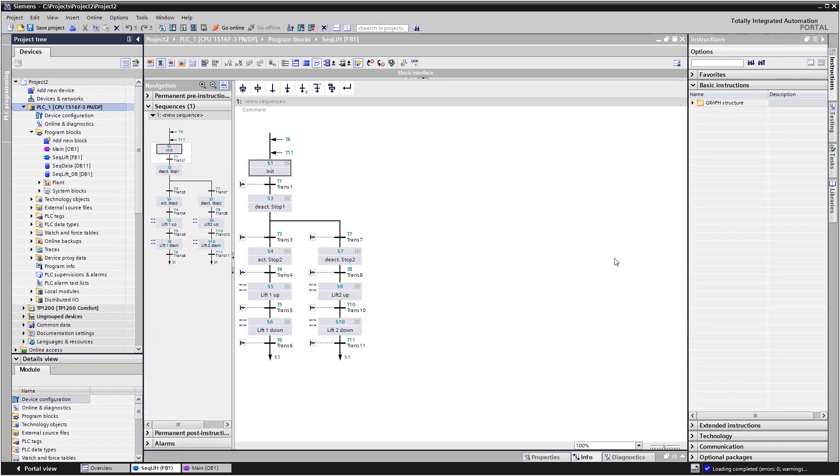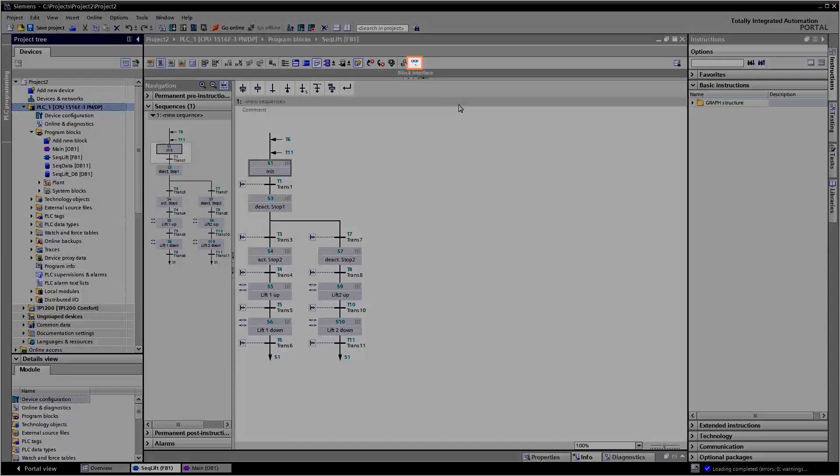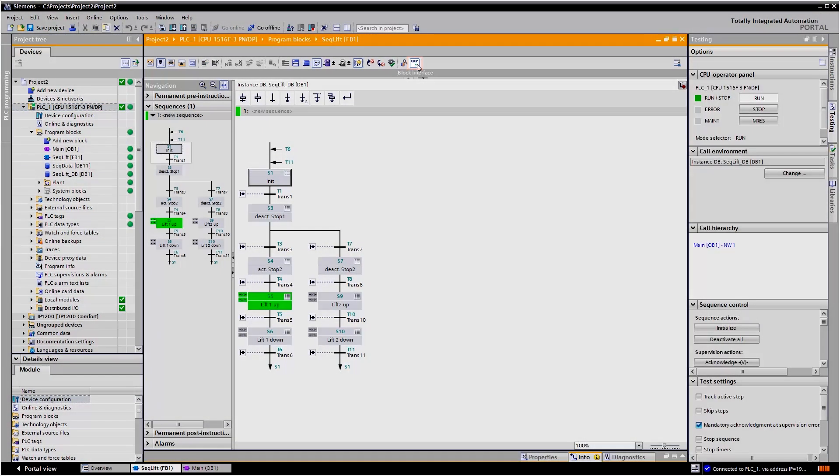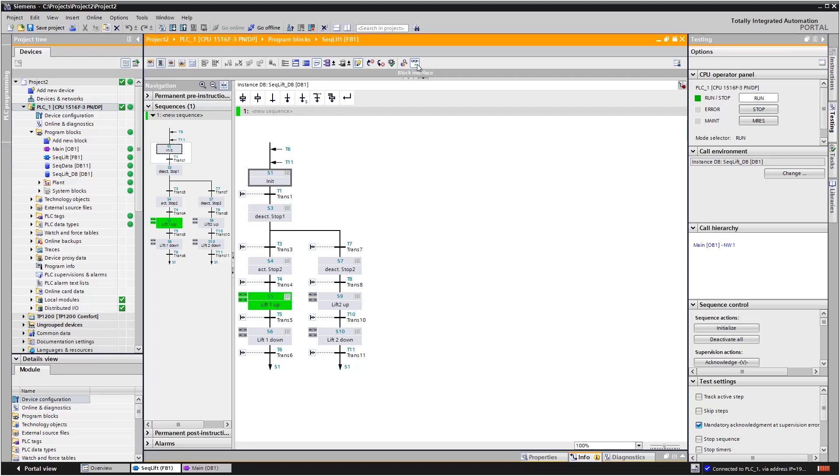By initiating the monitoring function, you can now monitor the sequencer online, both in the navigation tree and in the operating range. If there are faults in the routine, the step affected is marked in red. This greatly facilitates troubleshooting.